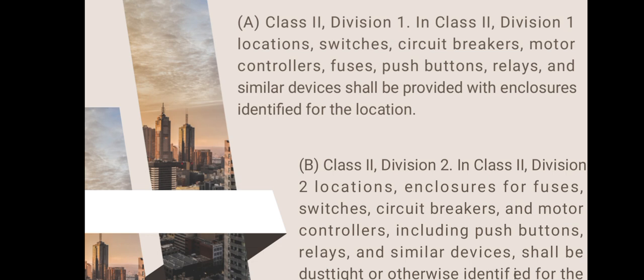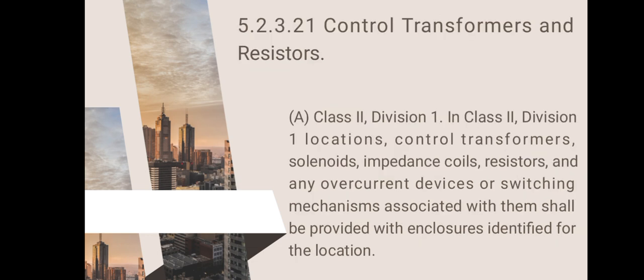So, for Class 2 locations, which include the combustible dust, in general, it must cover electrical equipment and wiring in locations where fire or explosion hazards exist due to combustible dust. Explosion-proof equipment is generally not required or acceptable unless also identified for Class 2 locations. In Division 1, combustible dust is present in the air under normal operating conditions in sufficient quantities to produce explosive or ignitable mixtures, or mechanical failure or abnormal operation might cause such mixtures to be produced.